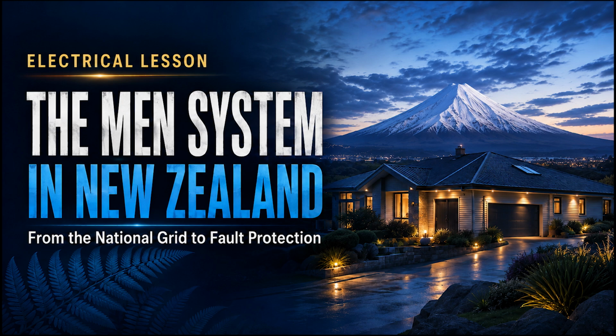Good. Then I ask, why will the MCB trip? The answer is often, because there is fault current. That is also a start. But now comes the important question. Can you draw the complete circuit followed by that fault current? Can you show where it leaves the transformer and exactly how it gets back to the transformer? And can you use Ohm's law to estimate how much current will flow?